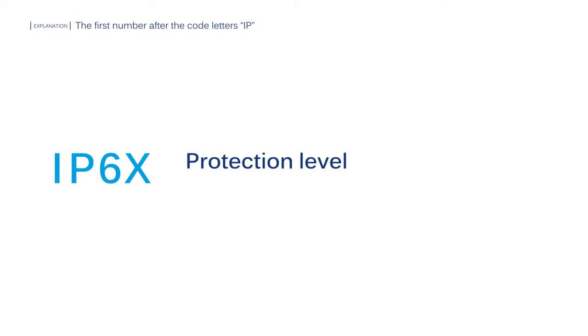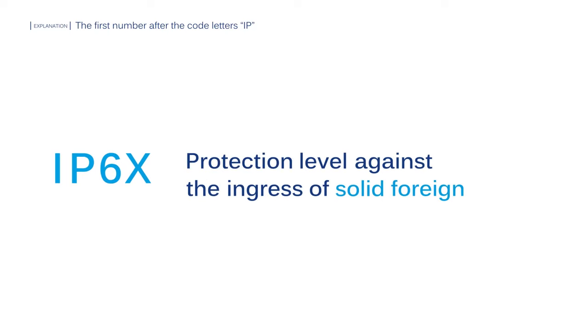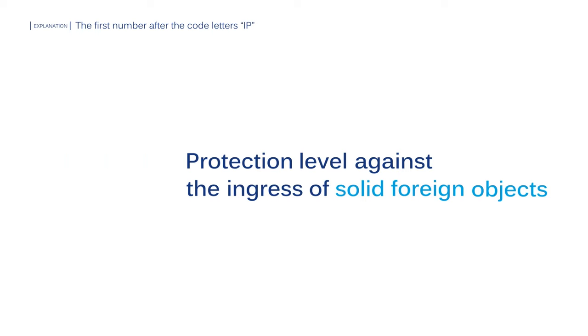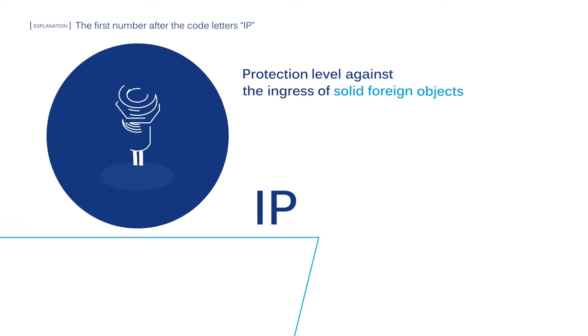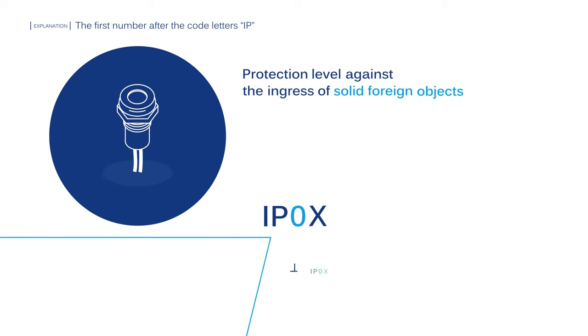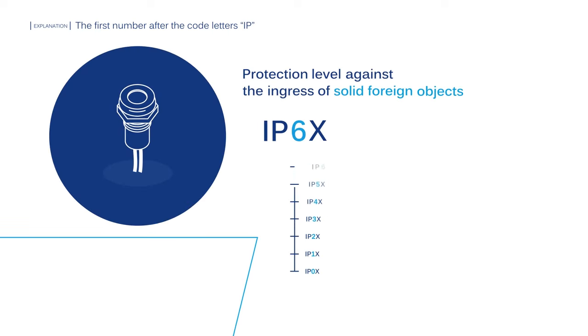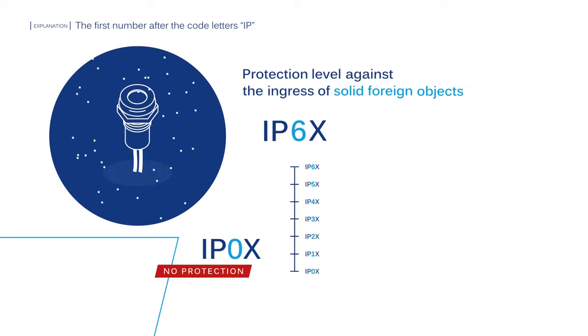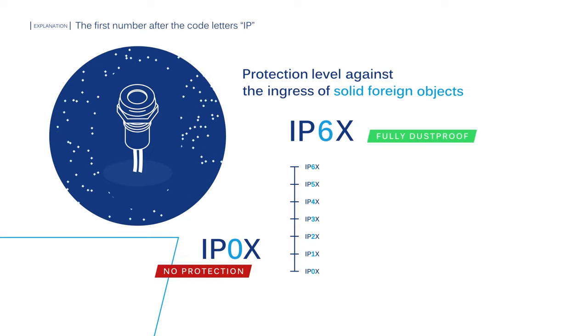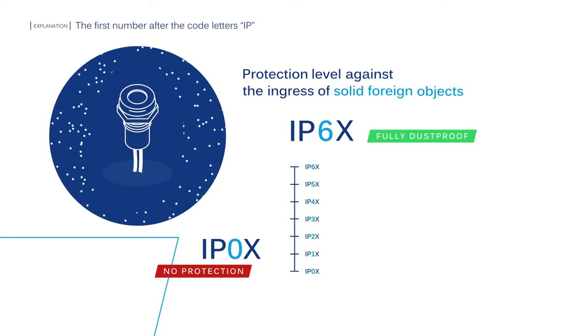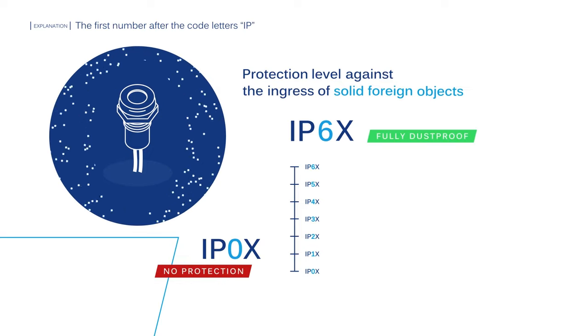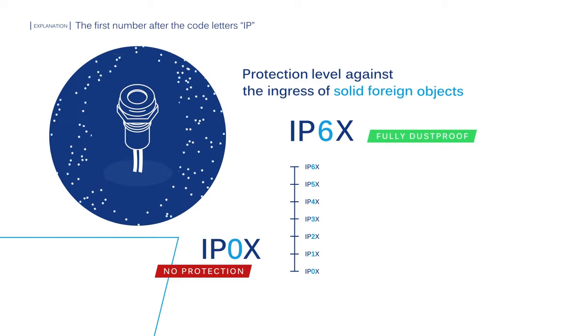The first number after the code letters IP refers to the protection level of the equipment against the ingress of solid foreign objects. The standard provides levels from 0 to 6, 0 being no protection and 6 being fully dust-proof and impenetrable with a 1mm wire.